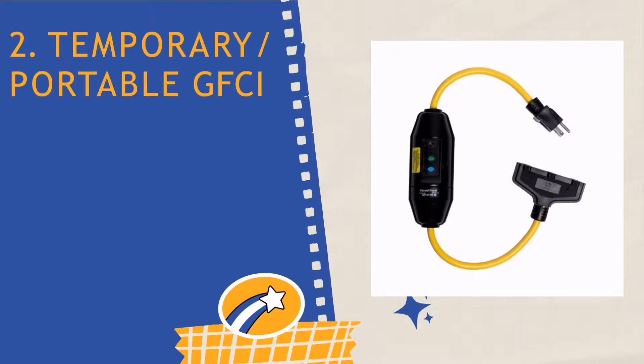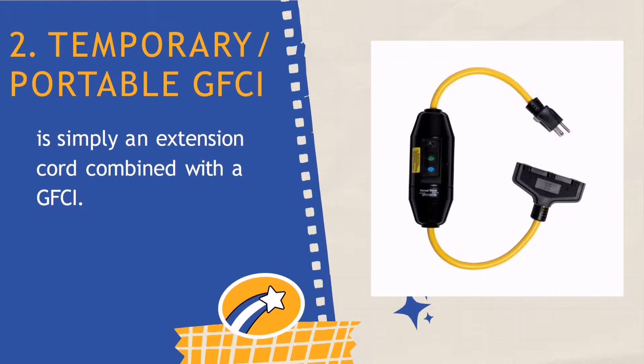Number 2: Temporary or Portable GFCI. When a permanent GFCI is not practical, a temporary GFCI is used. Temporary GFCI contains the GFCI circuitry in an enclosure with plug prongs at the back and receptacle plugs in front. It can be plugged into an unprotected outlet, and then the electrical appliance or device is plugged into the temporary GFCI. Portable GFCI is simply an extension cord combined with a GFCI. It adds flexibility in using receptacles that are not protected by GFCI. Extension cords with GFCI protection are great for use when a permanent or portable GFCI is unavailable.